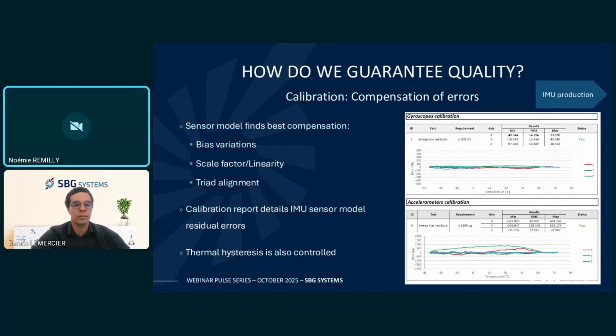Then when we have our model, we will do the calibration. Here I put an example of the gyroscope and accelerometer sweep bias residual. As you can see, it goes from 80 degrees C to minus 40 degrees C. And then we have some points of compensation where we will evaluate the bias variation, the linearity and scale factor of the sensor, and also the alignment between the sensor and the mechanical frame.